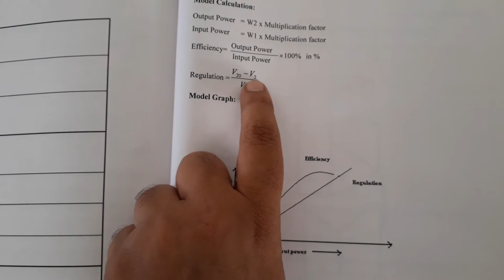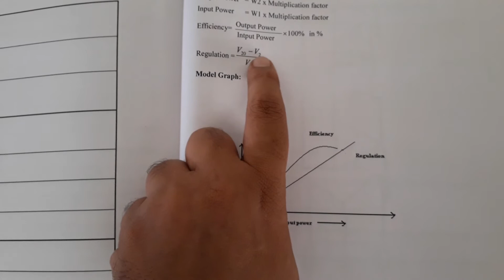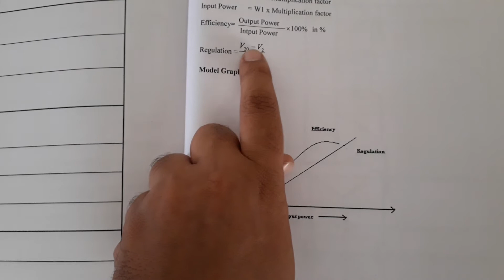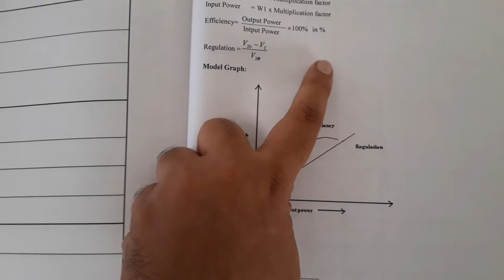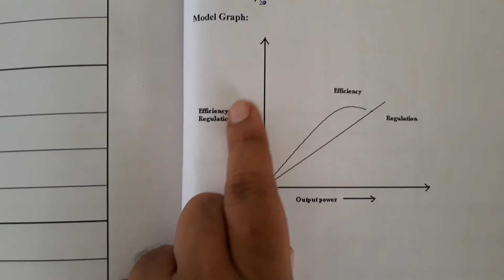Then if you keep on loading, for each loading the voltage will decrease by about 2 or 3 volts, up to 3 to 4 volts, for each 0.5 amps. So in the denominator you put the same no load voltage again. For example, 230 minus 227 divided by 230 for the particular load. For the particular load you have to calculate the regulation. Similarly, fill this column, the regulation column. Then plot the characteristics of percentage regulation versus output power.